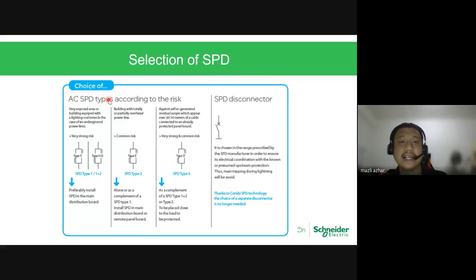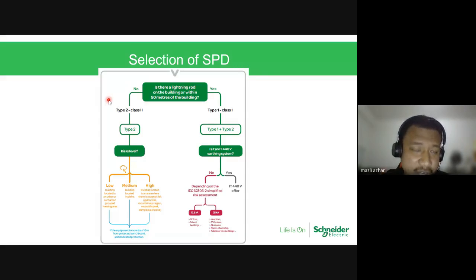So this is how you select. Or by Schneider Electric, we give this type of selection. Do you have a lightning rod in the building, 50 meters? If no, you go for type 2. And the risk level will need to be assessed. If the building is located in an urban or suburban group area, it's a very low risk. Medium, located in plains. When I talk about being located in plains, one building and the surrounding is like paddy field. Okay, so it's considered as a plain.